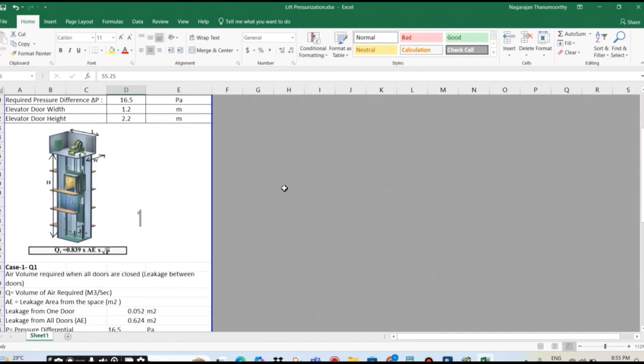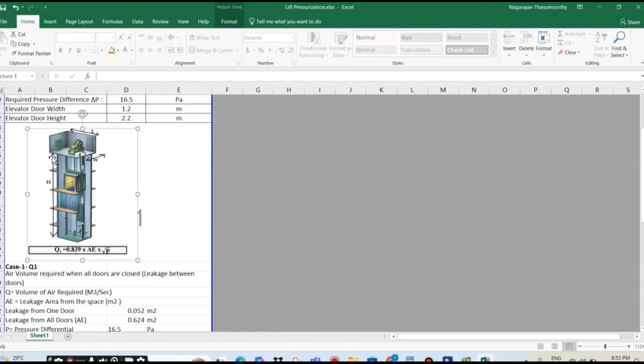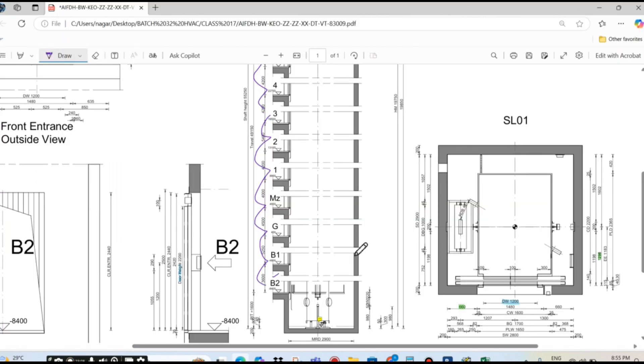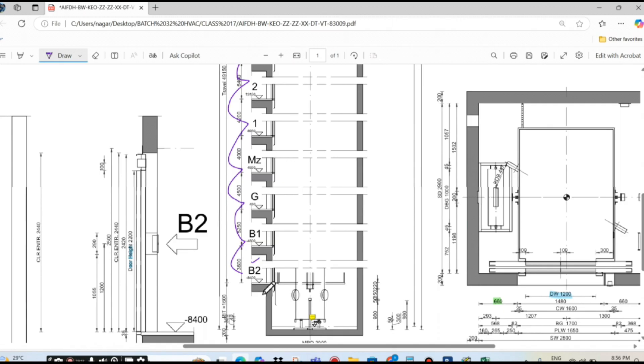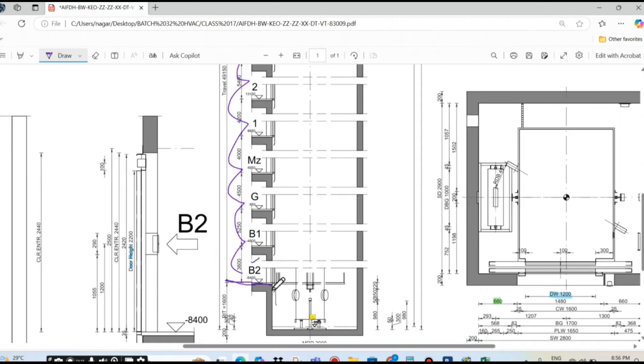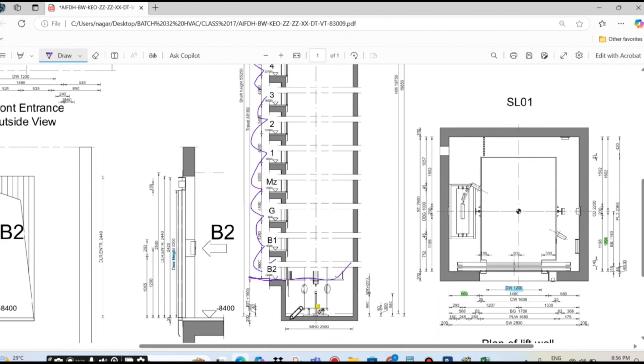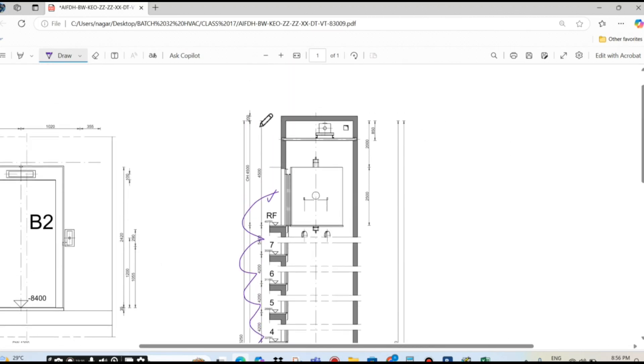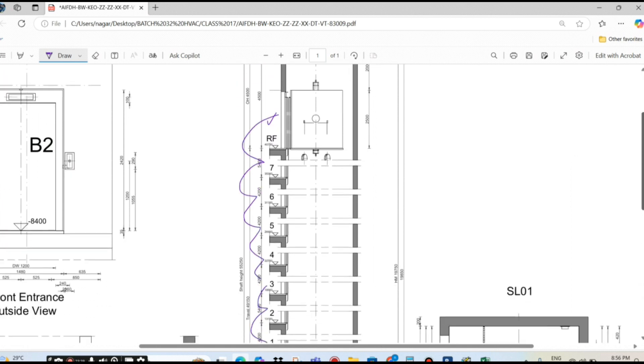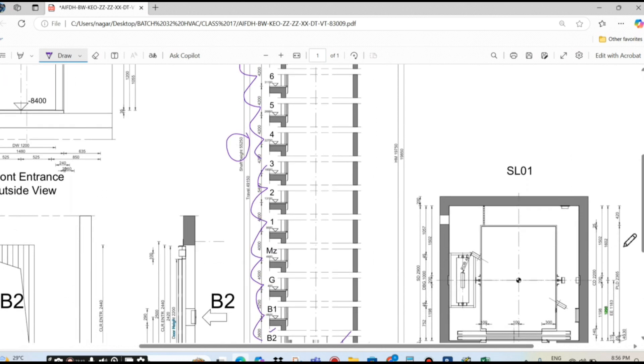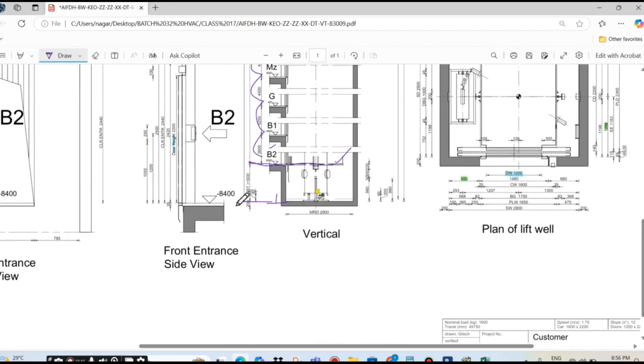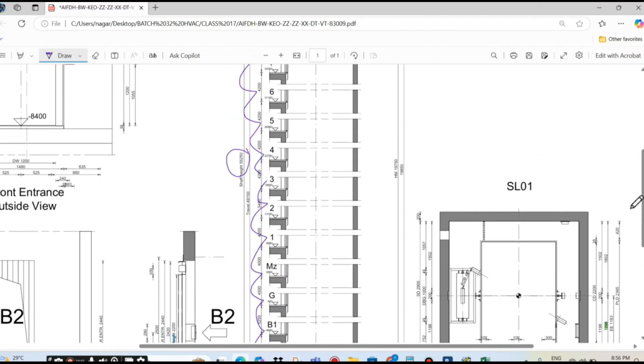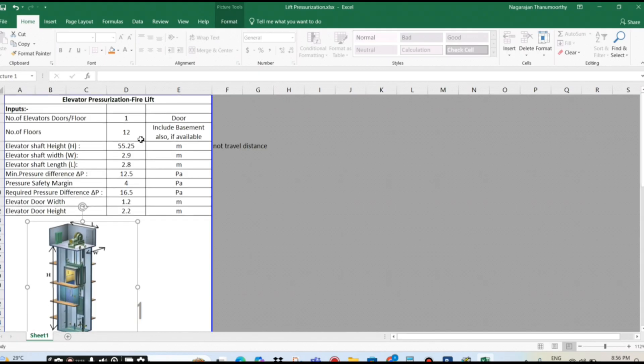For the elevator shaft height, we do the mistake normally. When we go for the height, normally some people will consider the height from the travel distance. Actually, this is the elevator travel distance. We actually need the distance from inside. So we should not use the travel distance — we need the internal height, same like what we did earlier. So we have to consider 55.250 — this is the total height from internal to internal, the same like a staircase. So this internal to internal, we are considering 55.250. That is the total shaft height: 55.250.